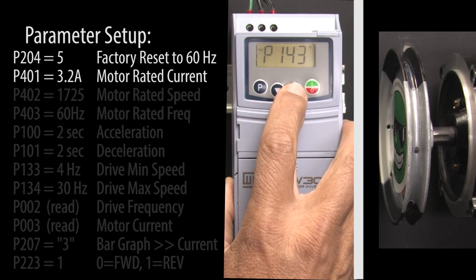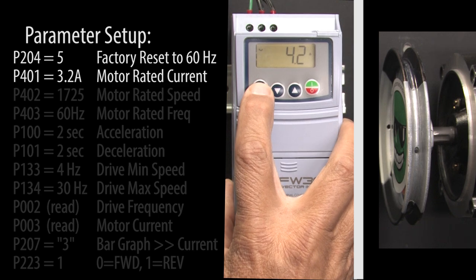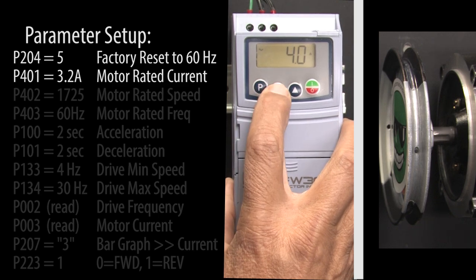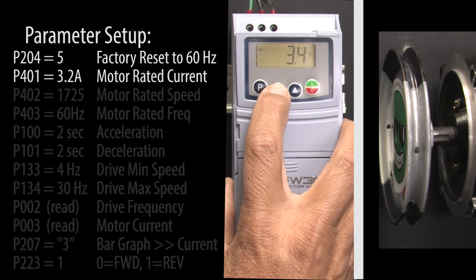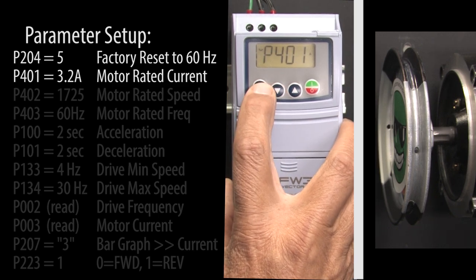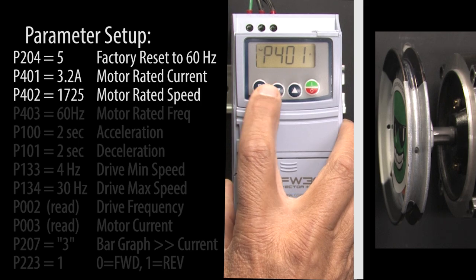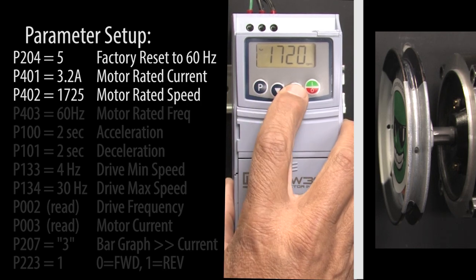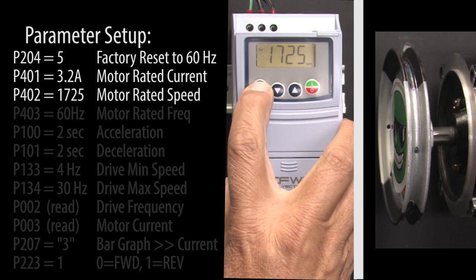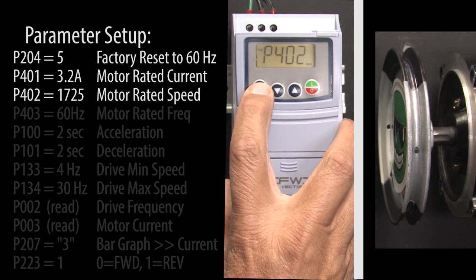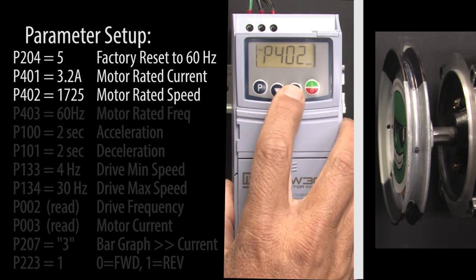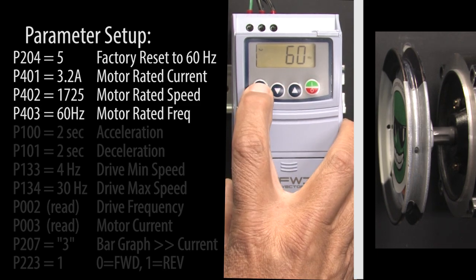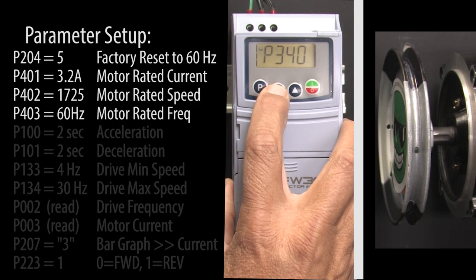Scroll to parameter 401, which is the motor's rated current. Ours is 3.2 amps, so we enter that and press P to accept it. Parameter 402 is the motor's rated speed — we'll modify that to 1725 and hit P to accept that. Parameter 403 is the motor's max frequency; 60 Hz is what we want, so hit P to accept that.